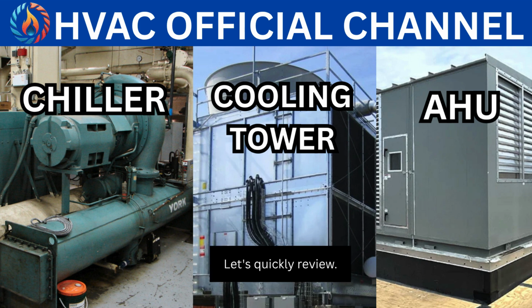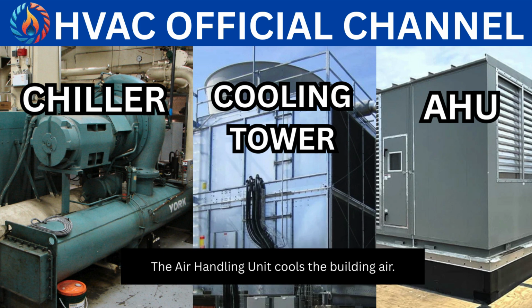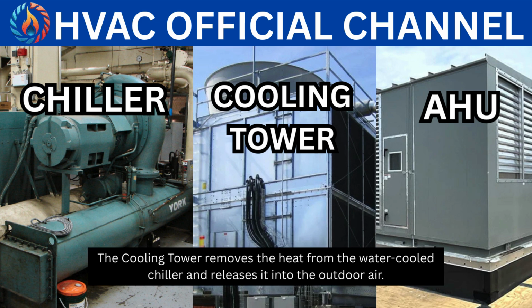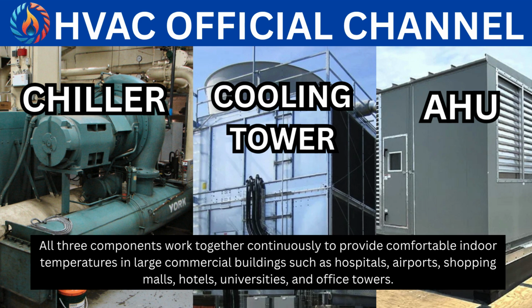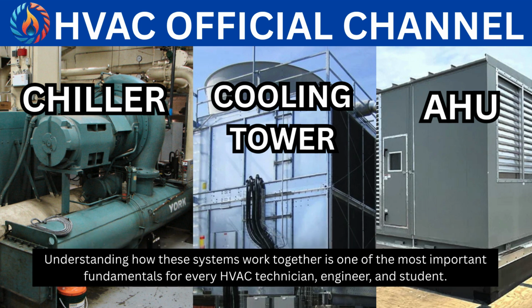Conclusion. Let's quickly review. The air handling unit cools the building air. The chiller cools the chilled water. The cooling tower removes the heat from the water-cooled chiller and releases it into the outdoor air. All three components work together continuously to provide comfortable indoor temperatures in large commercial buildings, such as hospitals, airports, shopping malls, hotels, universities, and office towers. Understanding how these systems work together is one of the most important fundamentals for every HVAC technician, engineer, and student.